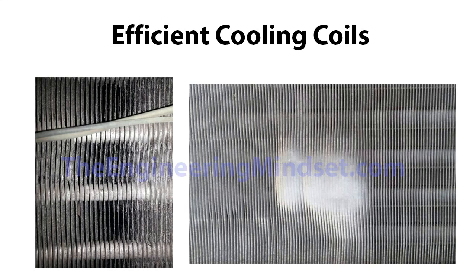Another very common issue with cooling coils is that the fins are very delicate, so any knock — if you're in there doing maintenance — has a high chance of damaging the fins, as you can see in the photo here. Someone has obviously knocked this cooling coil and actually closed the fins, pushing them shut so no air can pass through. That means no heat transfer will occur, because the air would normally pass through the gaps between the fins, but here they've been sealed.